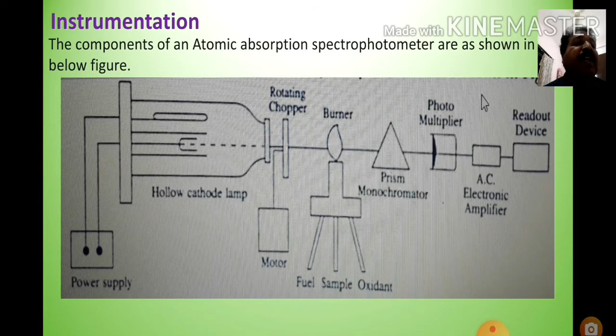The source of radiation should emit the radiation which can excite the atoms of the element from the ground state to the excited state. Hollow cathode lamp is used as a source of radiation. It consists of a hollow cathode cup made up of the element under study. For example, if you want to detect copper in the sample, then the lamp will have a hollow copper cup as a cathode. The cathode is protected in a glass shield.